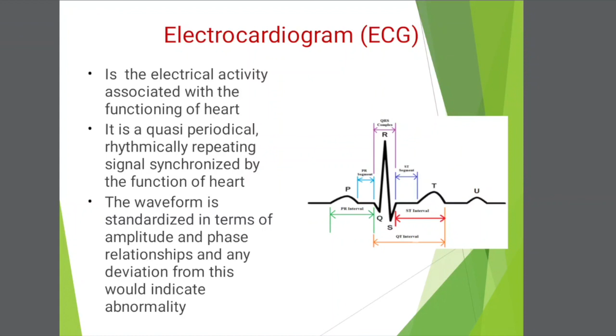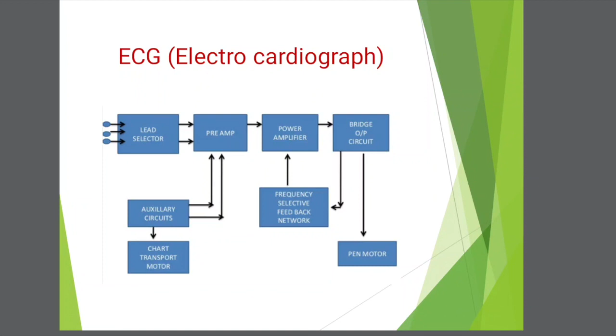The main blocks of the electrocardiogram are lead selector, preamplifier, power amplifier, bridge output circuit, then auxiliary circuit, chart transport motor, frequency selective feedback network, and pen motor. The potentials are picked up by the patient electrodes. Each pair of electrodes conveys certain information. So for the appropriate waveform or view, we have to select an appropriate lead pair.